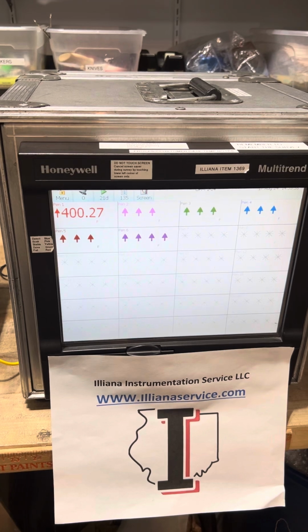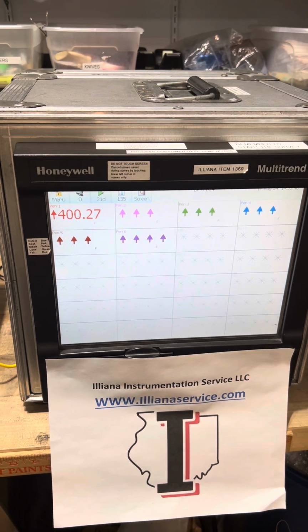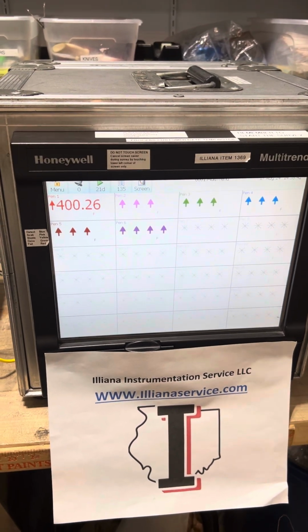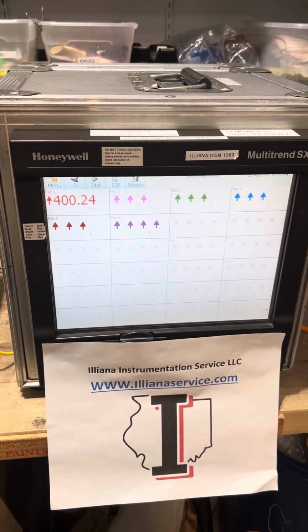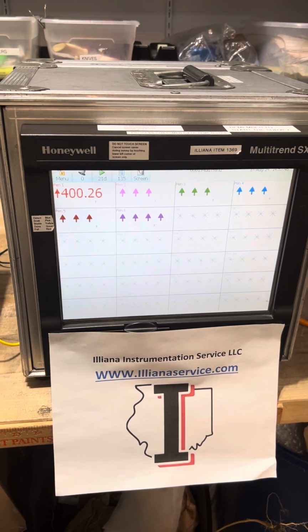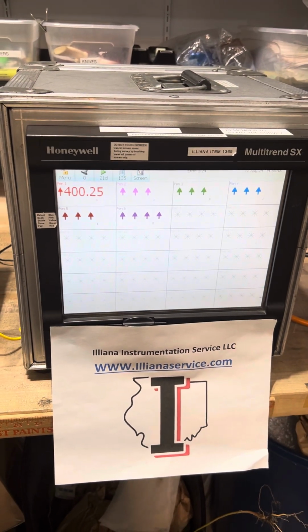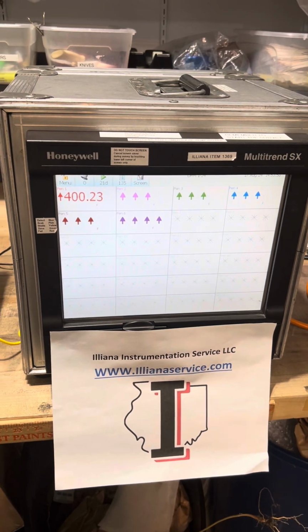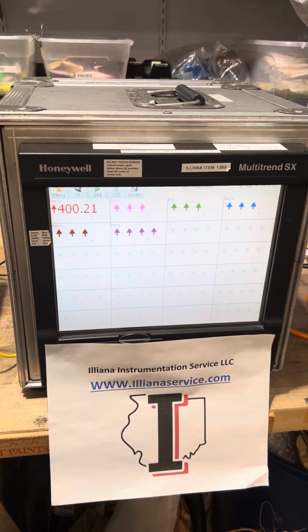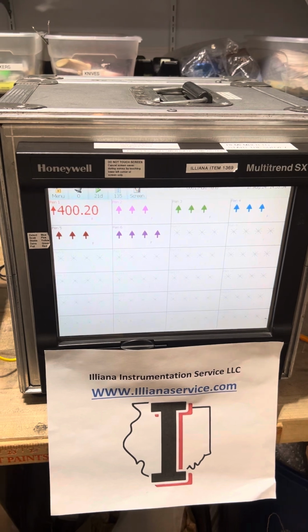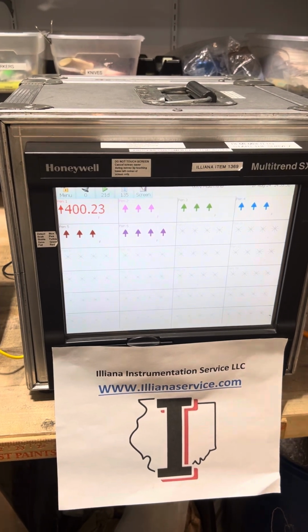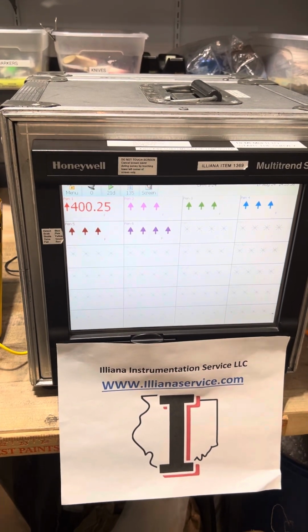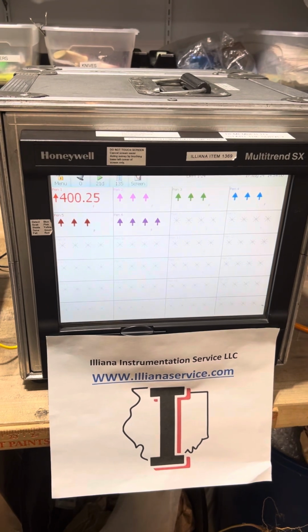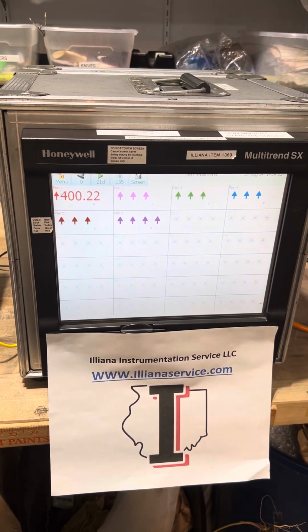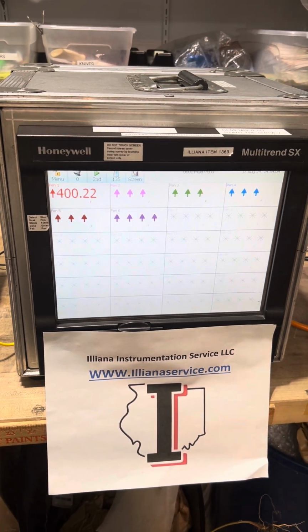Typically AMS 2750 requires a 6-point calibration on thermocouple ranges over your qualified operating range. So if you were using this thing 0 to 1,000 degrees, you'd put in probably 0 and 1,000, and then 4 other points evenly distributed in there to do your calibration. Typically those numbers are just going to be a couple of tenths, and that's going to properly calibrate the recorder.